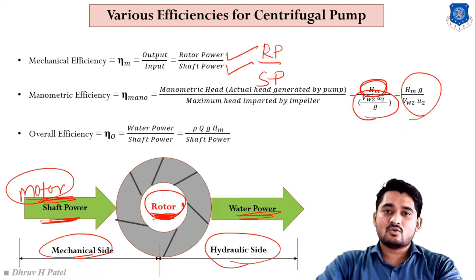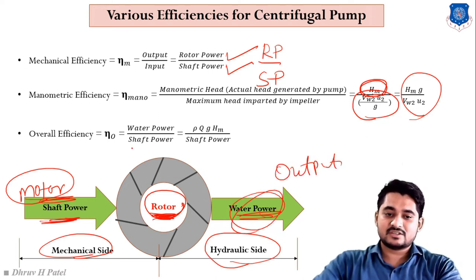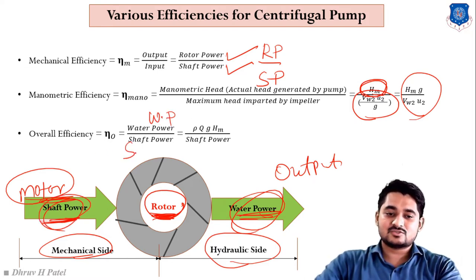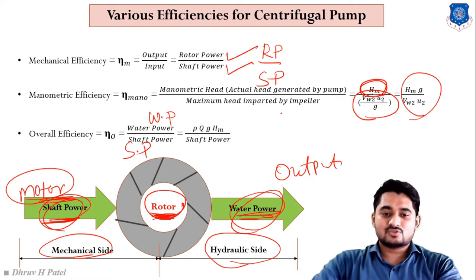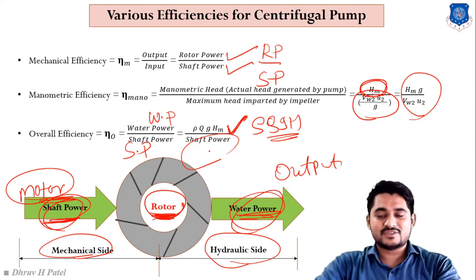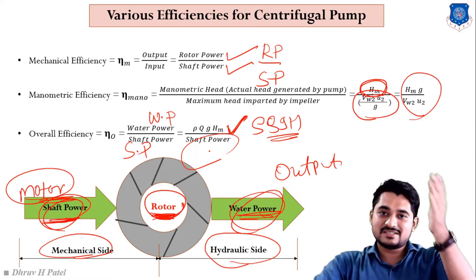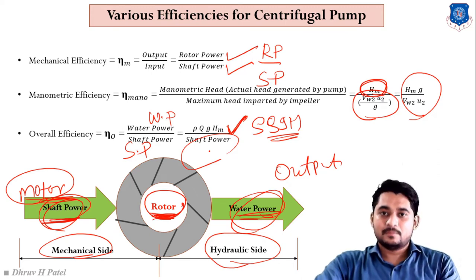Next is overall efficiency — the overall action of the centrifugal pump. Output of the centrifugal pump is water power (WP) and input is shaft power (SP). Water power at output is ρQgH, which is the potential energy of the water. So overall efficiency equals water power divided by shaft power.